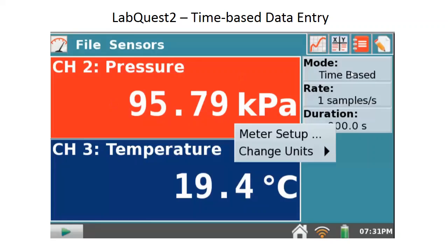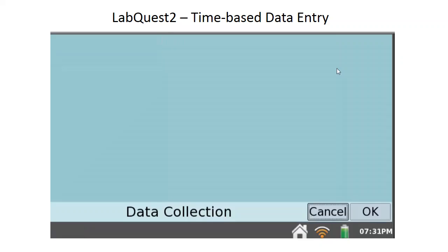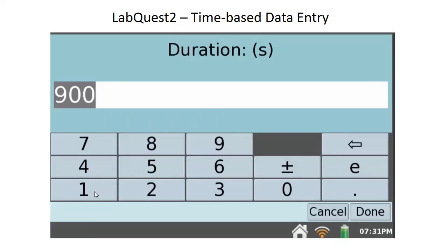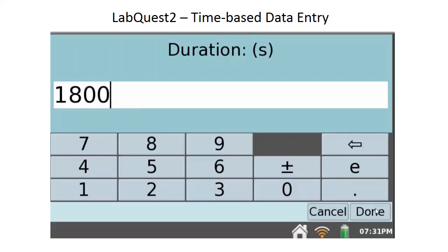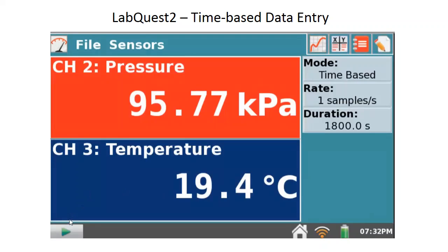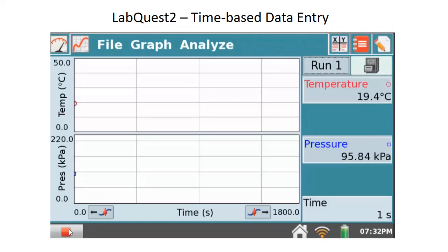If I go up to where it says time-based and click on it, I can set the duration — let's say 1800 seconds, though you can always stop the run whenever you want. So I set my time to 1800. When I look at what my plot will look like and start the run, I'll see two graphs: one is temperature and one is pressure, both plotted against time. I'd really like to see my pressure against temperature, not time.